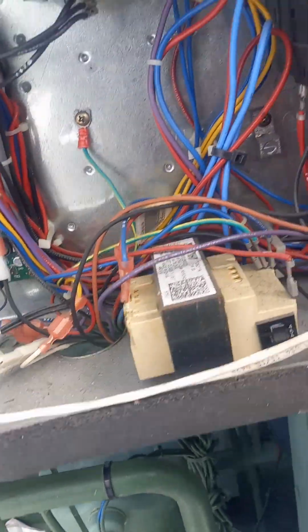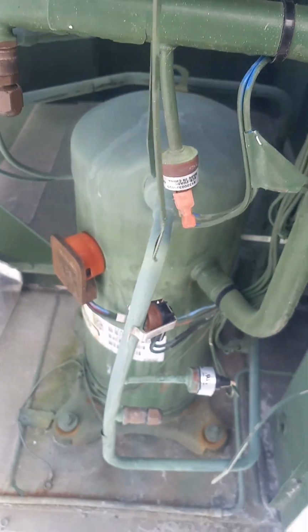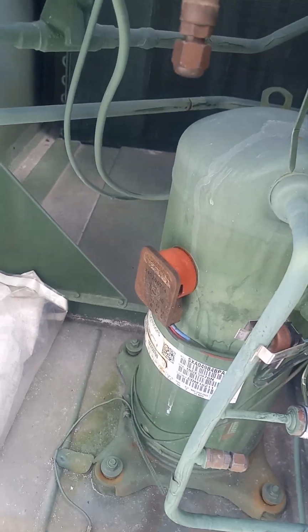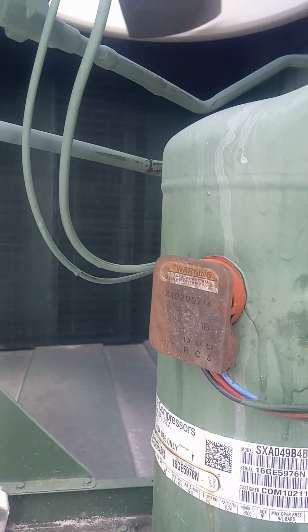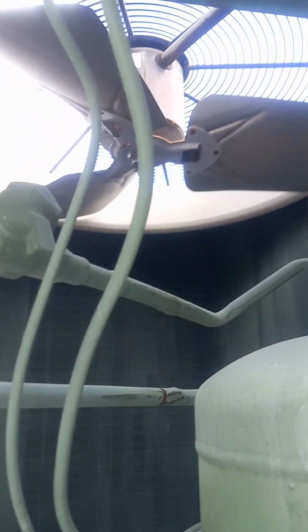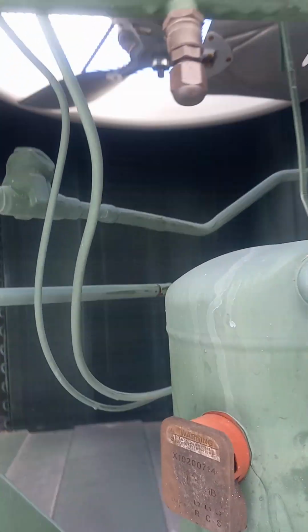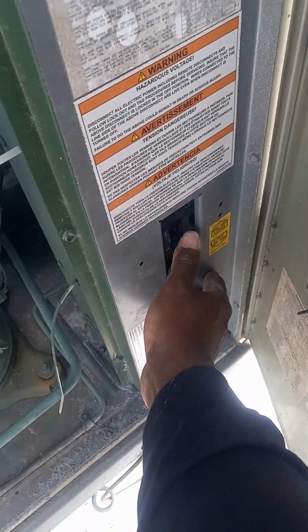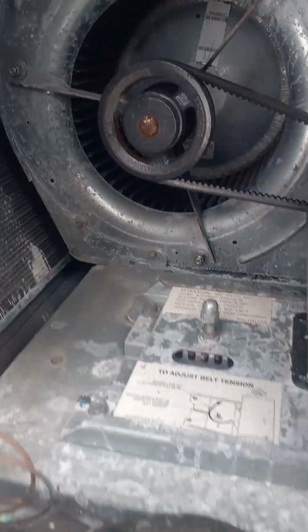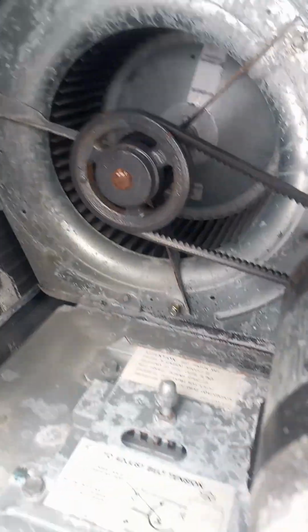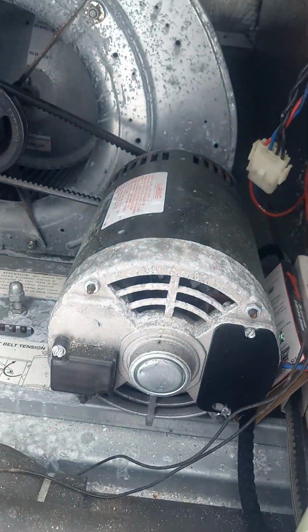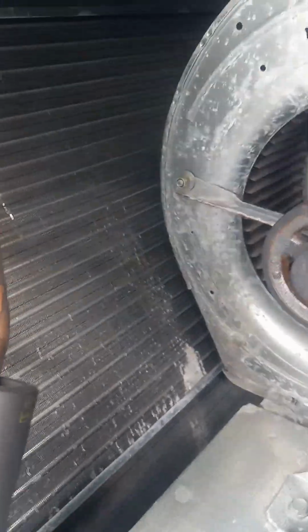And the high voltage, as I said, that's the contactor for the compressor. This right here is the compressor. The compressor works with the condenser. The condenser is like copper coils with fins, and then that's the condenser fan motor. Inside here, let me shut down this unit real quick. Unit is dead. So this is the blower compartment, right? This blower has a blower wheel, the blower motor, which is still high voltage, a belt that runs it, and the evaporator coil.